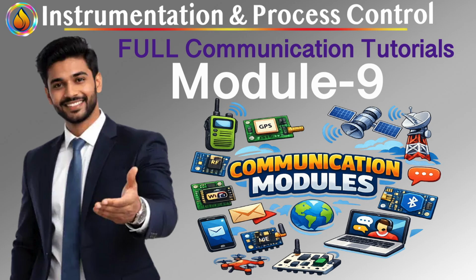In bus-powered segments, devices draw operating power from the bus. Power and data share the same pair. Every device adds electrical load. Foundation Fieldbus H1 and many DeviceNet segments fall here. Now, segment design becomes an electrical budgeting exercise. You must account for steady-state current, startup current, voltage drop along the trunk, spur resistance, power supply headroom.